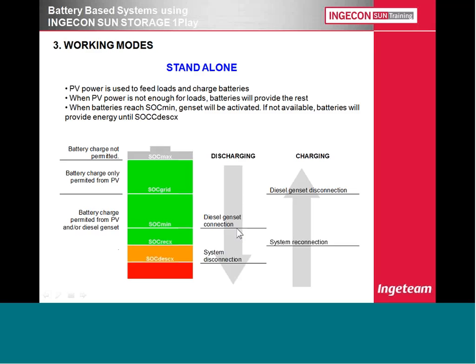So once again, all these parameters have to be configured at the inverter through the display. So this is how it works, okay? Basically, your batteries will start working when the grid disappears, and then they will reach whatever point. And once you reach that point, you will start charging them again till you reach the maximum value. In order to reach that value, from here to here, in this range, you can take power from the grid. Sorry, this is not correct, it should be the grid, not diesel genset, because this is actually connected to the grid. And from this point on, you have to charge the batteries taking power from the PV only. Okay? So this is how it works.